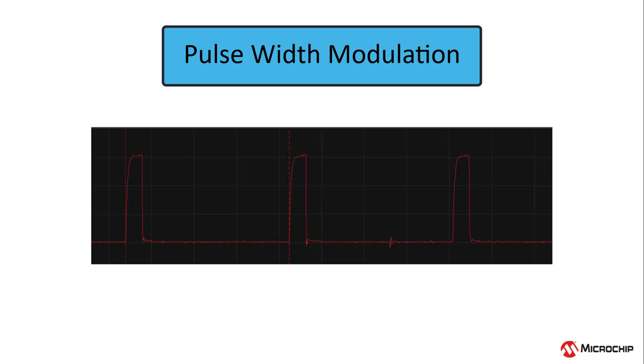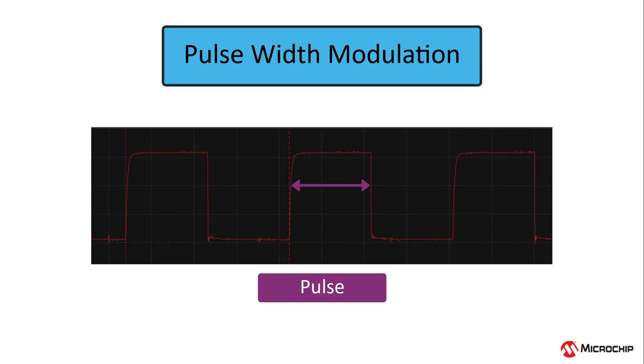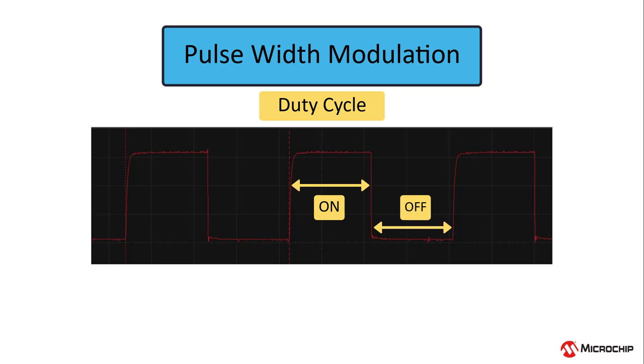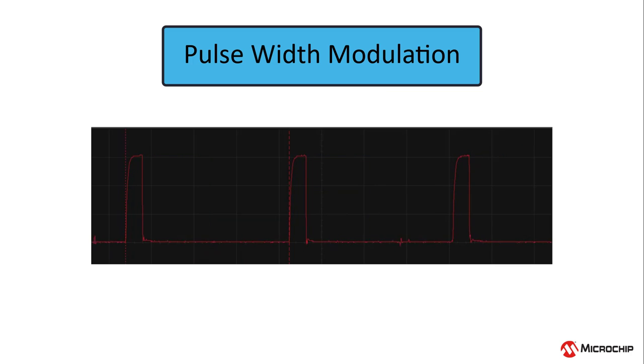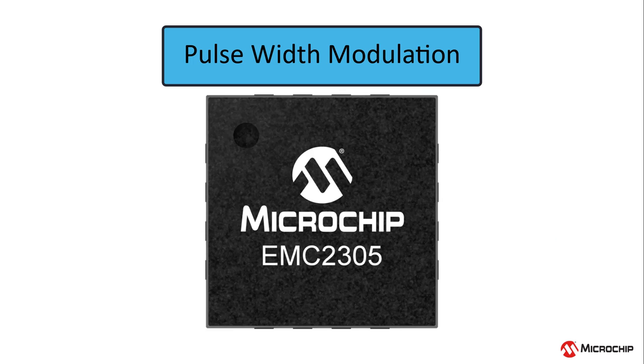The PWM signal is a very common method used to control the speed of the fan. It's what the name implies: a pulse sent to the fan driver circuitry whose width can be modulated based on the desired speed. The term duty cycle is used to describe the ratio of how long the pulse is on versus off. A 50% duty cycle means the pulse is on 50% of the time and off 50% of the time. A 10% duty cycle would mean it's on 10% of the time and off 90% of the time.